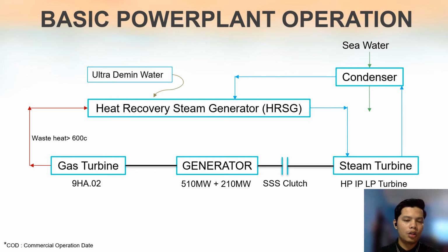So this is the basic power plant operation. From the gas turbine, it will generate a waste heat at about 600 degree and above. The waste heat will be used to supply at heat recovery steam generator, or we call as HRSG. This HRSG will generate a high pressure of dry steam by using ultra demineralized water. This high pressure dry steam then will go to the steam turbine to be rotated. The steam turbine consists of high pressure turbine, intermediate pressure turbine and low pressure turbine. The dry steam will flow through all these parts.